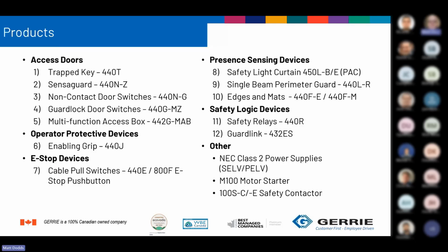So the 12 groups of products covered in this presentation relate to more standalone safeguarding or devices that interface into a safety PLC. We will not be covering the safety PLCs themselves, but we will be talking about the peripheral devices. So we have devices for access doors, trap key, Sensaguard, other non-contact switches, guard lock door switches, and the multifunction access box. We'll touch on enabling grips, and then go into e-stop devices, cable pull and e-stop push buttons. Presence sensing devices, safety light curtains, single beam perimeter guard, edges and mats, and then safety logic devices, the 440R relay and GuardLink. And then as time permits, we'll cover some additional topics that relate to safety with respect to things that are required.